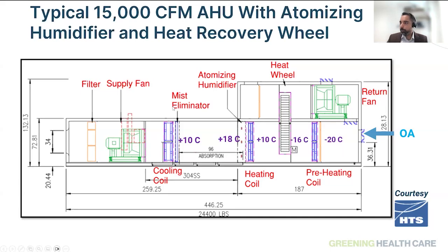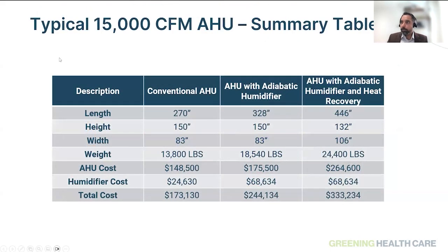Let me continue. Here's just a quick comparison in terms of the length, weight, and cost for these systems. As you can notice, the cost increases from a conventional unit because we're adding adiabatic humidification and also adding an enthalpy wheel. But overall, it provides you a better solution which reduces the overall emissions in your facility, because now you're not relying on steam. And you're also recovering heat from the exhaust, which was previously not an option in your case. You're offsetting your natural gas consumption in your building by doing that.